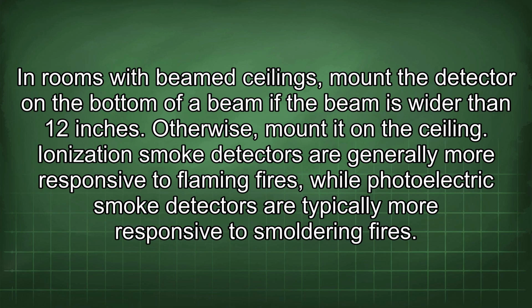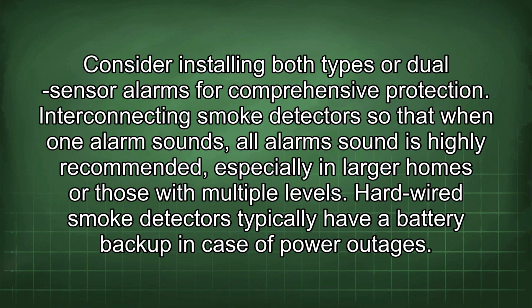Ionization smoke detectors are generally more responsive to flaming fires, while photoelectric smoke detectors are typically more responsive to smoldering fires. Consider installing both types or dual sensor alarms for comprehensive protection. Interconnecting smoke detectors so that when one alarm sounds, all alarms sound is highly recommended, especially in larger homes or those with multiple levels. Hardwired smoke detectors typically have a battery backup in case of power outages.